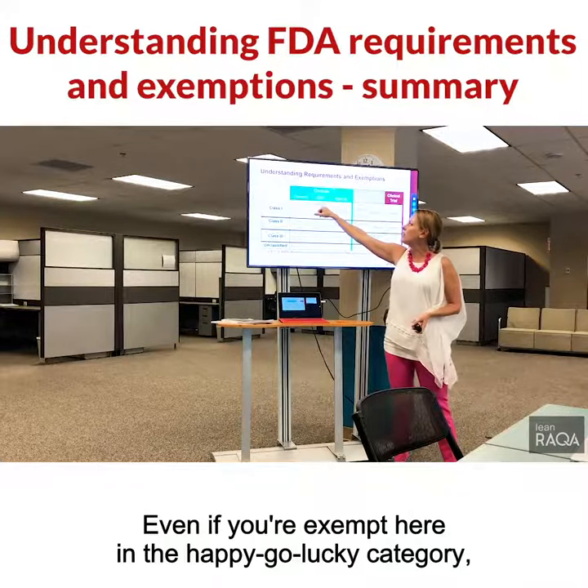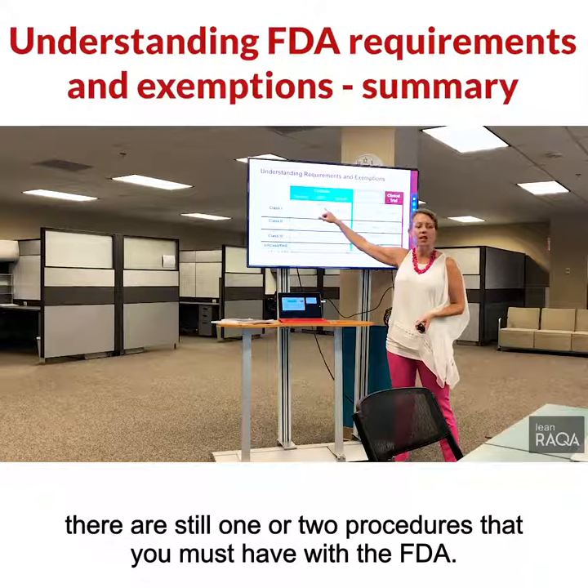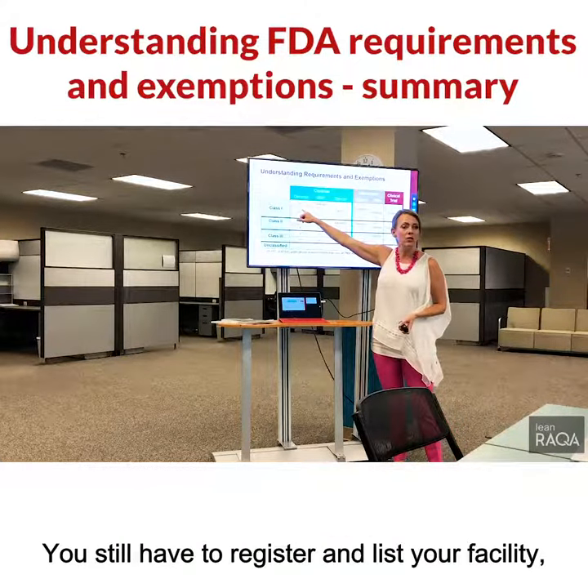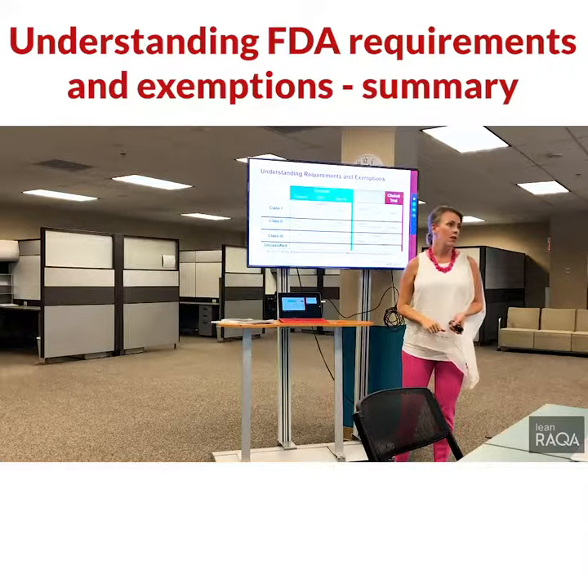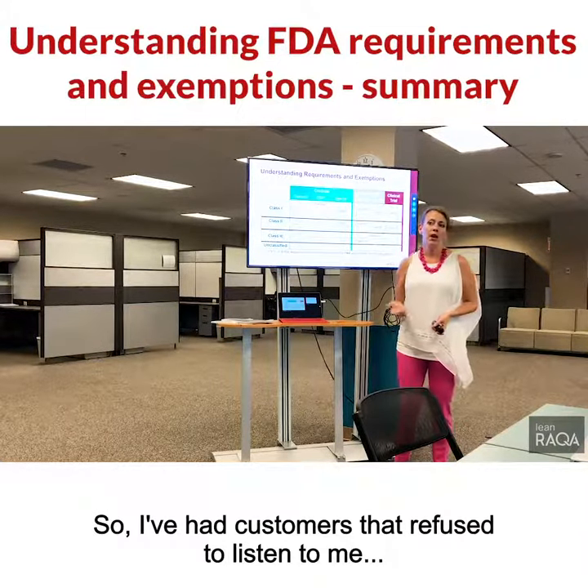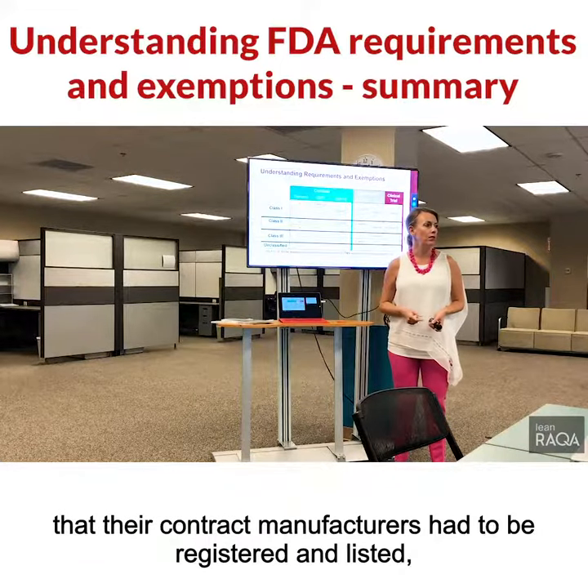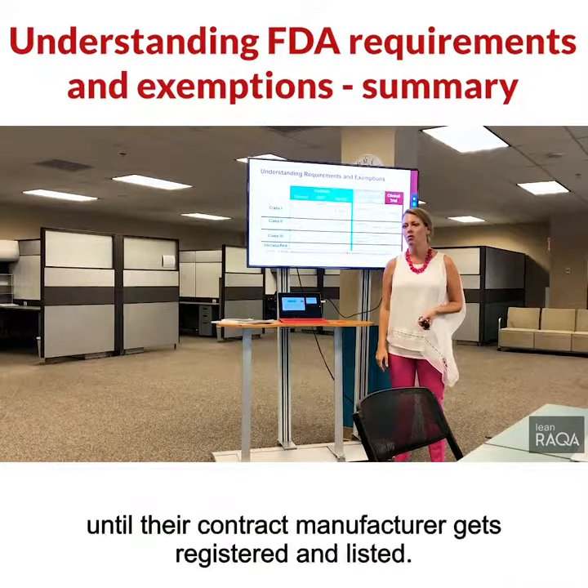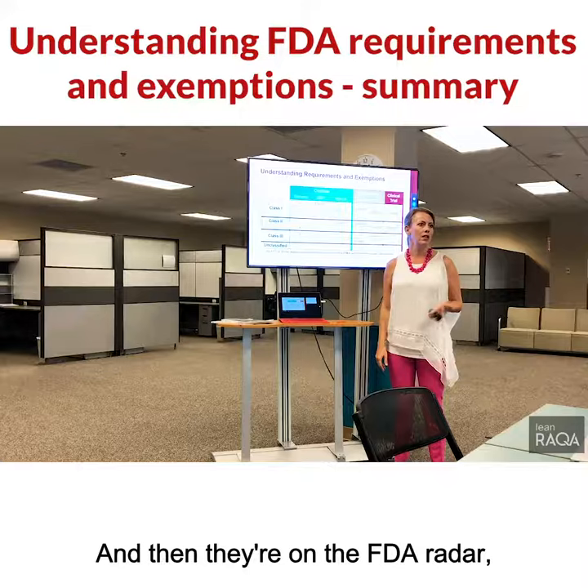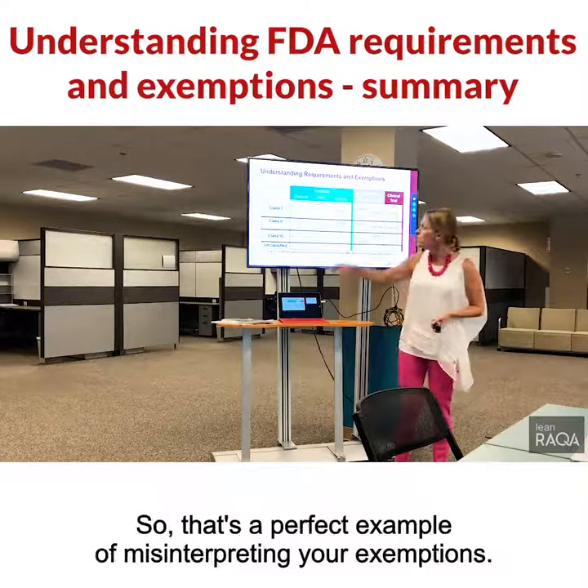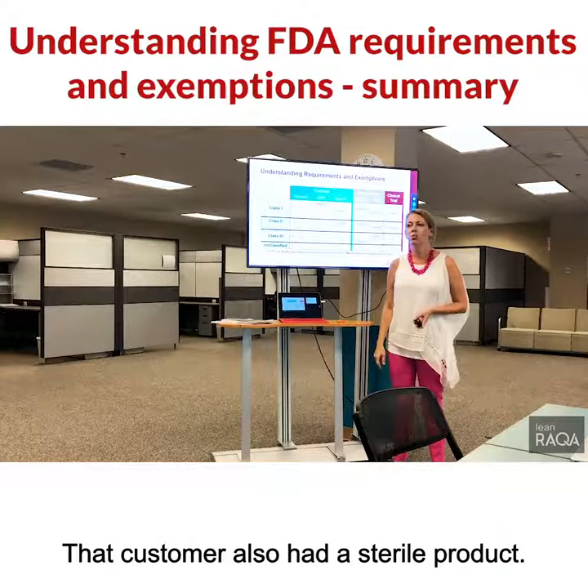Even if you're exempt in the happy-go-lucky category, there are still one or two procedures that you must have with the FDA. You still have to register and list your facility, and your contractors still have to register and list their facility. I've had customers that refused to listen to me that their contract manufacturers had to be registered and listed, and then they got their products stuck in customs until their contract manufacturer gets registered and listed. Then they're on the FDA radar, and not in a good way. So that's a perfect example of misinterpreting your exemptions.